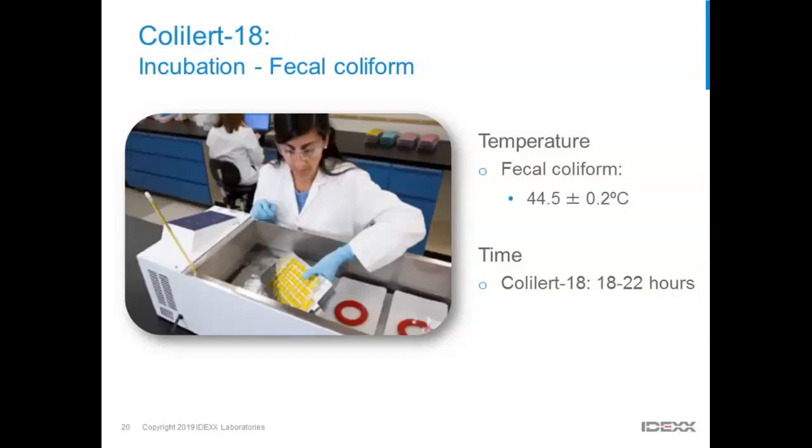What you don't want to use is something like a rock or brick, which will weigh it down but has a good chance of also breaking it. You also don't want to use something like a beaker full of water or a bottle. That kind of item can throw off the thermodynamics of the whole system, which might create some issues with results. So you want to make sure you use the appropriate way to weigh down the trays and keep them below the surface of the water in the water bath.